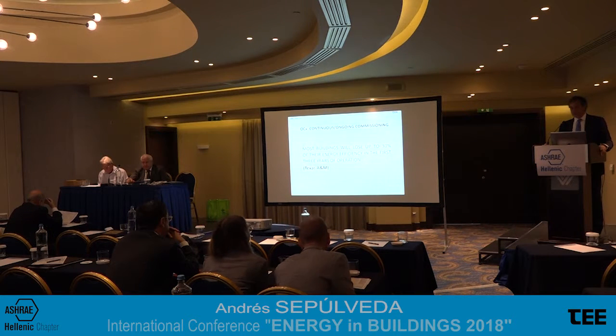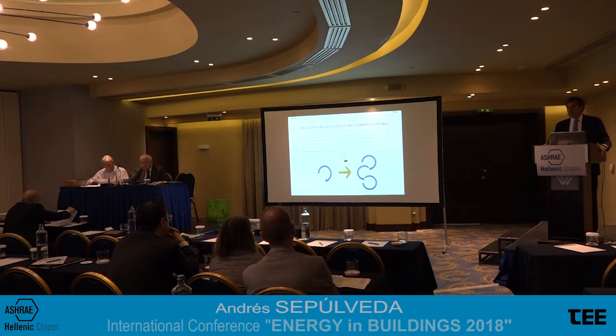Of course, it's a pity, but we see that most buildings lose their energy efficiency in the first 3 years of operation. That is why it's so important, after the handover, whether it's a newly constructed building or a major renovated building, to have a continuation of the commissioning process in order to monitor that these requirements, call it the current facility requirements, are met during the life of the building.